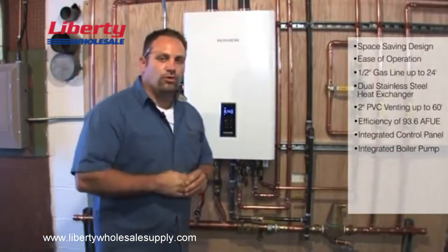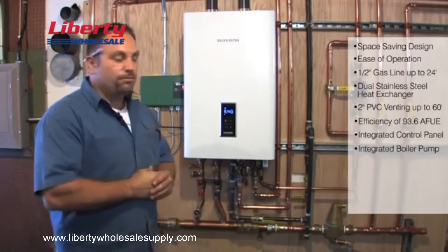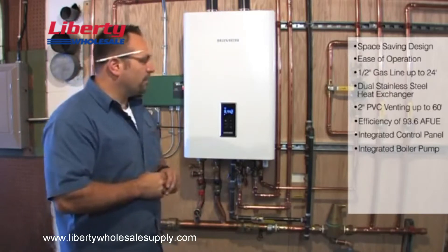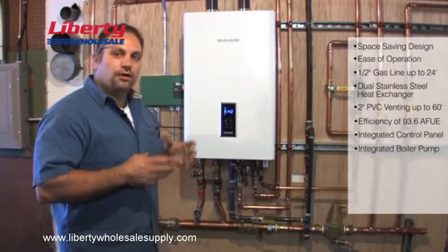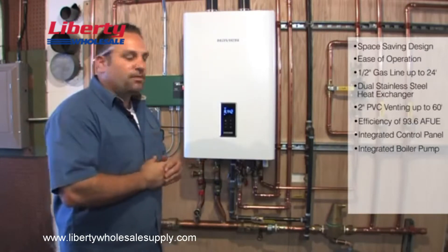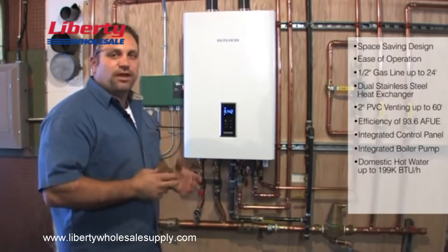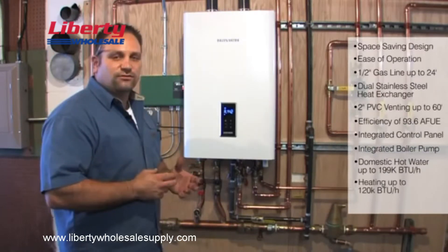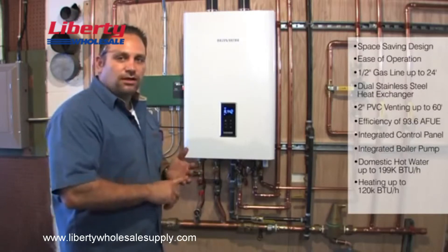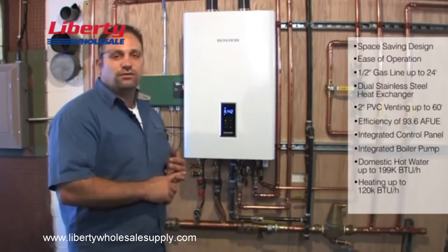To touch on a couple more very important features and capabilities of the unit: the Navien is the only unit on the market that can supply you with enough domestic hot water and enough space heating capability. It has 199,000 BTU capability for the domestic and up to 120,000 BTU for space heating. Space heating could be radiant floor, air handler type, or radiant tubing going around the house as fin tube heaters.